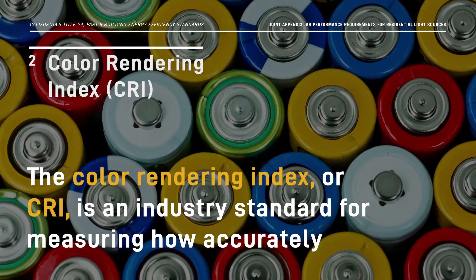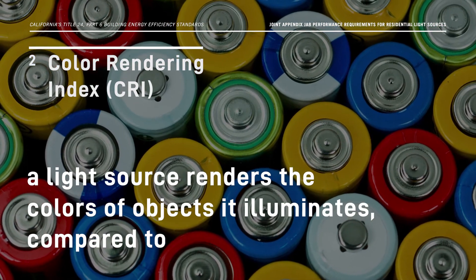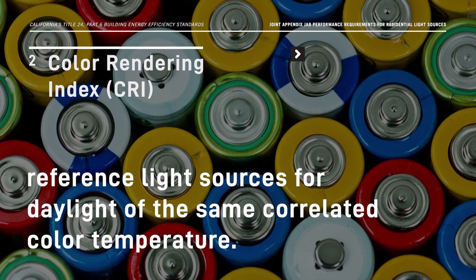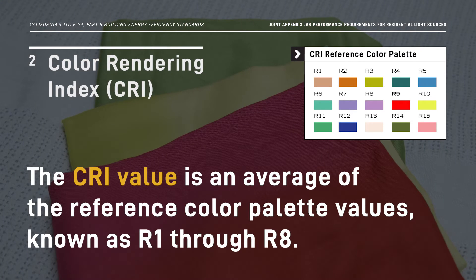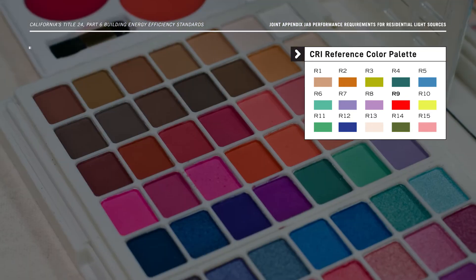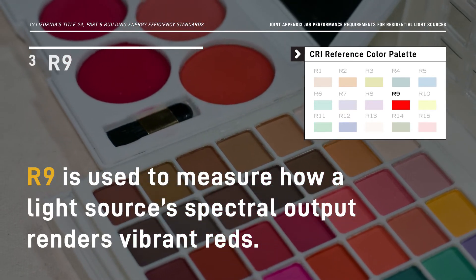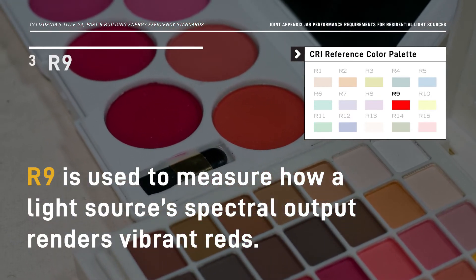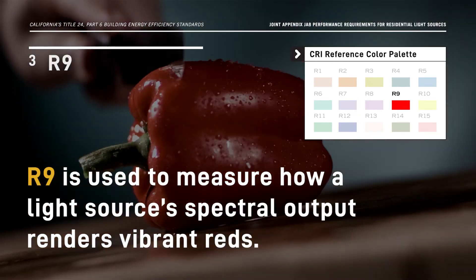The Color Rendering Index, or CRI, is an industry standard for measuring how accurately a light source renders the colors of objects it illuminates compared to reference light sources for daylight of the same correlated color temperature. The CRI value is an average of the individual reference color palette values known as R1 through R8, and the maximum CRI value is 100. The reference color palette R9 is used to measure how a light source's spectral output renders vibrant reds — an important consideration when illuminating items with natural reds, including some skin tones, food, and wood.